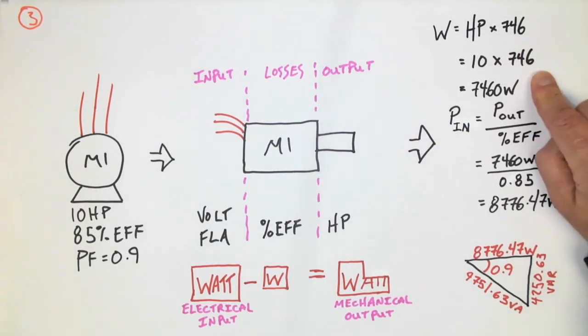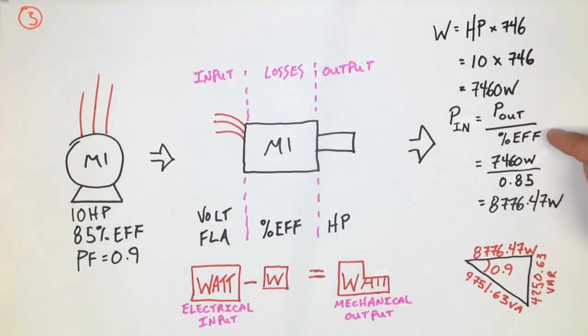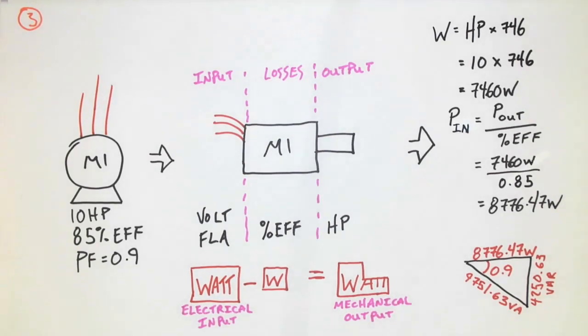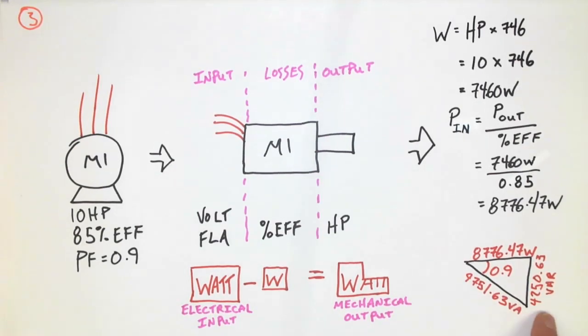For the 10-horsepower motor, we multiply 10 by 746, which gives us 7,460 watts output — that is the output power at the shaft. Using the percent efficiency formula, power input equals power output divided by percent efficiency, so 7,460 divided by 0.85 equals 8,776.47 watts input. We then use the power factor given in the question: watts divided by power factor gives total VA. I use Pythagoras to get the VAR value.